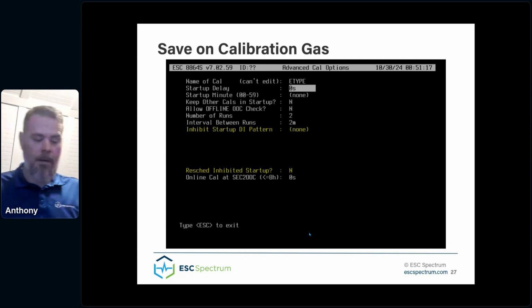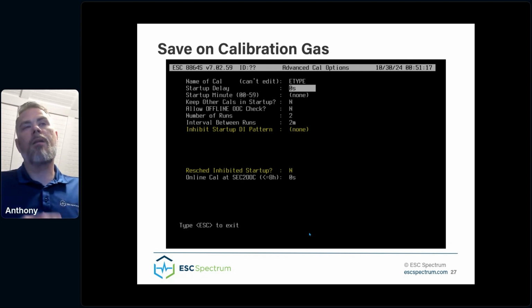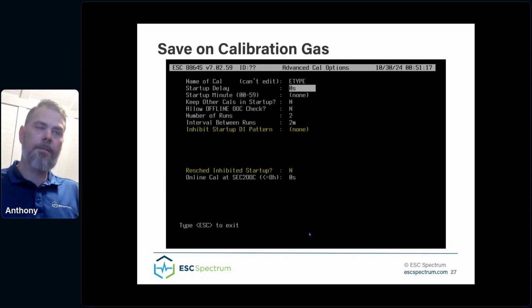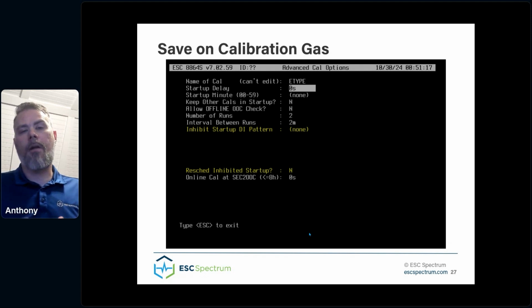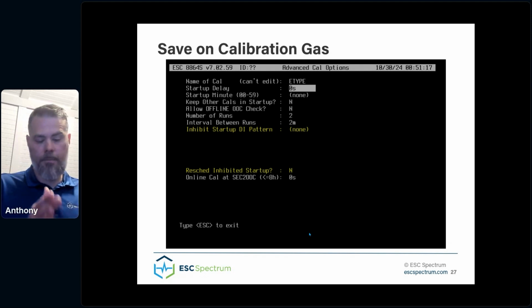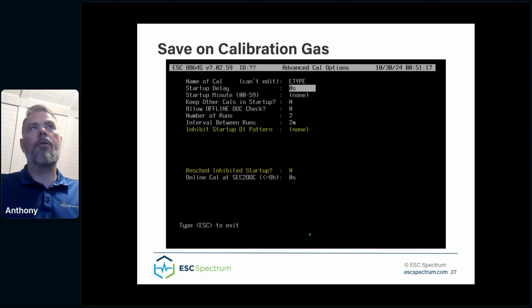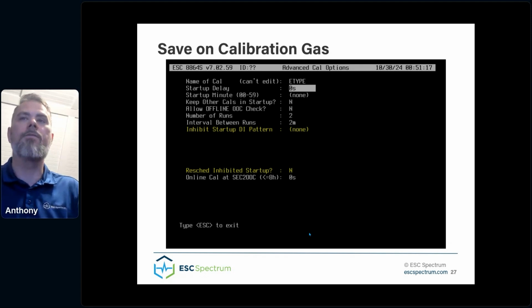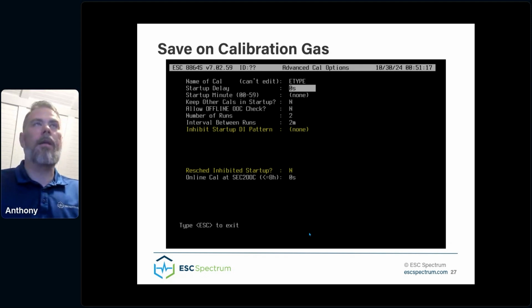This is the same as if you had a startup calibration scheduled, but you went offline. So the data controller already knows not to run that cal, but to schedule it an hour later because maybe you will be online. And that happens till the grace period ends. That's all already there. This follows that same logic and same pattern. If it's set to no, an inhibited startup calibration is not rescheduled during the grace period unless you have another fully offline hour, in which case it will reschedule the startup calibration. However, if your inhibit pattern remains, then it will prevent that calibration from running.